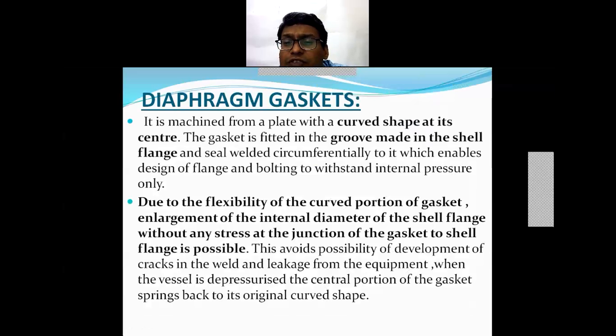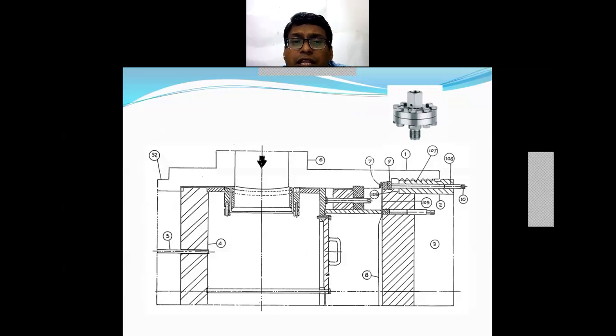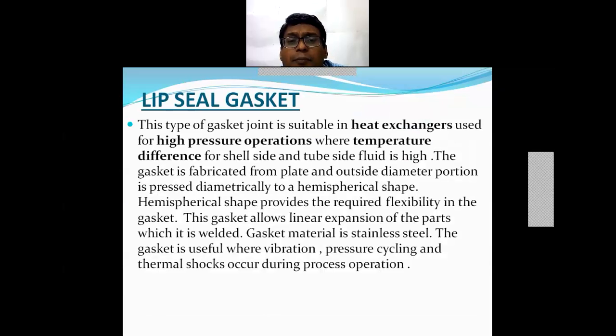So due to the flexibility of the curved portion of the gasket, the enlargement of the internal diameter of the shell flange without any stress at the junction of the gasket to the shell, that is possible. The next is a lip seal gasket. This type of a gasket joint is suitable in the heat exchanger again for the high pressure and temperature operations. The gasket is fabricated from the plate and outside diameter portion is pressed diametrically to the hemispherical shape. This hemispherical shape provides the required flexibility in the gasket.